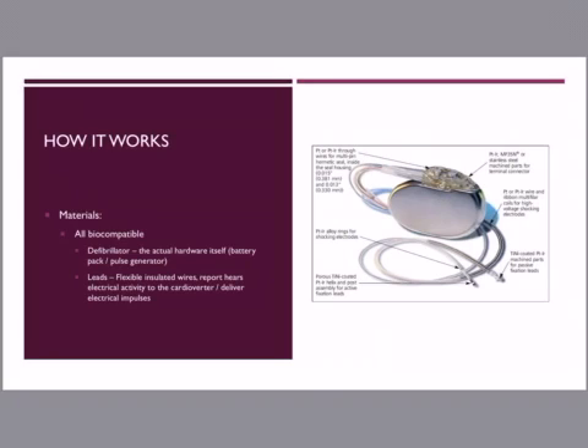The leads of the device are flexible insulated wires that monitor the electrical impulses and report the heart's electrical activity back to the implantable cardioverter defibrillator. These leads deliver charges from the generator to the heart when needed, as well as sending the signal back and forth. The way that this all works is that the defibrillator has a program that it follows to monitor the heart, and it makes decisions based off the frequencies that it's obtaining to make the certain adjustments that need to be made to the heart's rhythm.